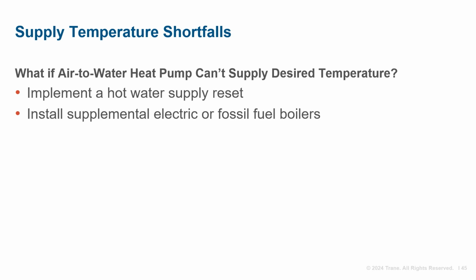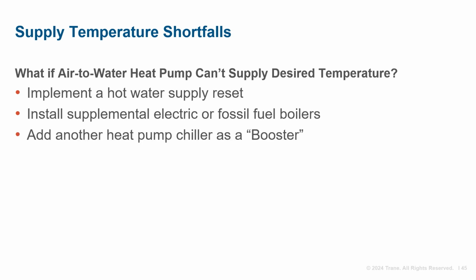Second, supplemental electric or fossil fuel boilers may be used to reach higher hot water supply temperatures. In many cases, the building might have an existing boiler that could be used for this purpose at no additional first cost to the building owner. The downside is that these units have low efficiencies and potentially high carbon emissions. A third option would be to add another unit in a booster arrangement to reach the required hot water supply temperature.